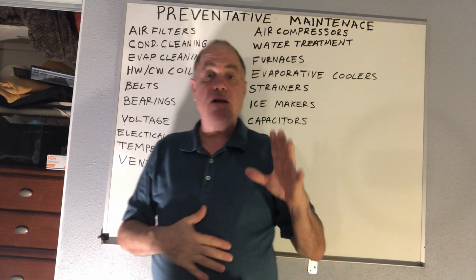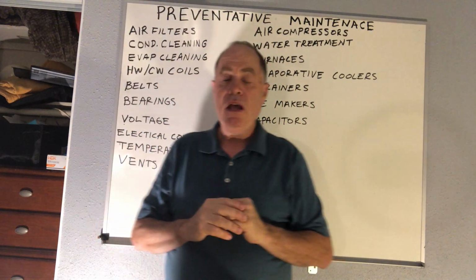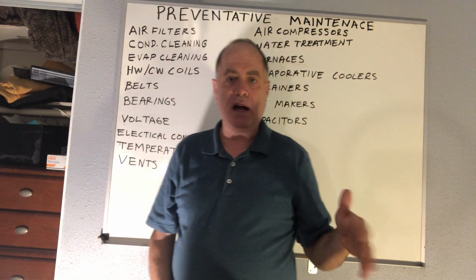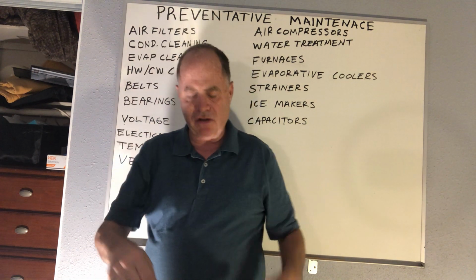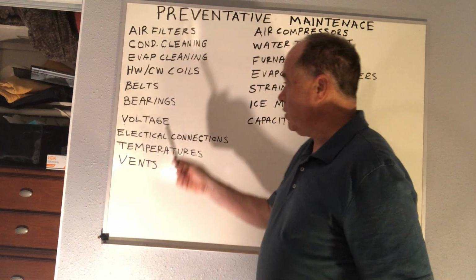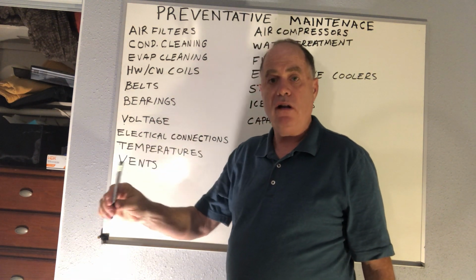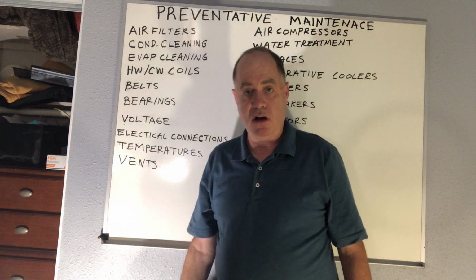On the other hand, if you have a ball bearing that takes grease and it doesn't run that many hours in a year, and it's in a pretty stable, cool environment, maybe you only need to lubricate it every couple of years. Okay? So there are some guidelines there for maintaining bearings, but figure out what is going to work for you, where you actually have time to do the maintenance on it.